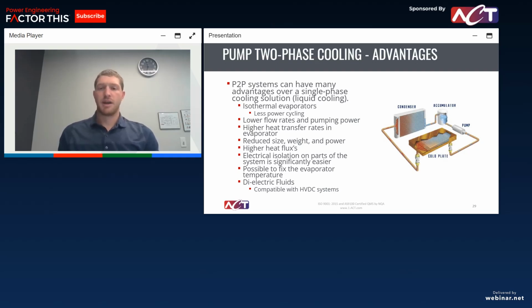Another great advantage is with high heat flux components working in a two-phase solution, you can isolate those components. We'll get into some internal evaporator designs, but you can isolate those components and meet those cooling needs. Oftentimes we'll see with anything over 100 watts per square centimeter, single phase cooling is not really able to achieve that cooling and keep them as cool as you need. Two-phase, we have had pump two-phase designs that have got up to even a kilowatt per centimeter squared. So there's a lot of advantages there in how much you can do with those high heat flux components.